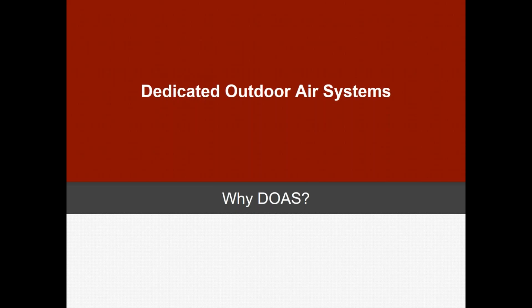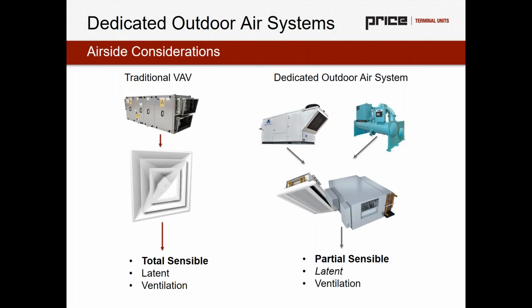It's the idea of why we utilize dedicated outdoor air systems. The reality of our dedicated outdoor air system is best summarized by the airside consideration in comparison to traditional VAV. When we look at a traditional VAV system, that airside portion of the system is responsible for all sensible cooling, latent cooling, and ventilation. A dedicated outdoor air system operates on the core belief that we should only provide the minimum amount of outdoor air required for ventilation and for latent loads. We're looking at a partial sensible airside solution. That outdoor air is only providing part of the sensible load. It's taking care of the latent load and ventilation airflow as well.